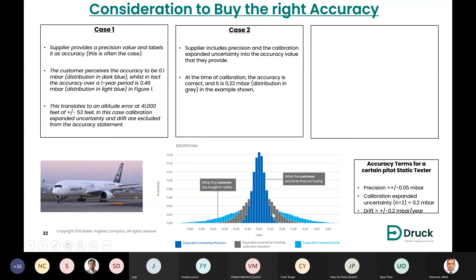Case number 2. The supplier will write the specs with the precision and calibration expanded uncertainty, and he will neglect the drift. The drift is the change of the behavior of the sensor over time. Everything, after some time, will have some decrease in its performance. This is what we call the drift. At the time of calibration, when the device is manufactured and calibrated in the factory, it was correct. It was 0.22 millibar, which is in gray. So here are the claimed specs.